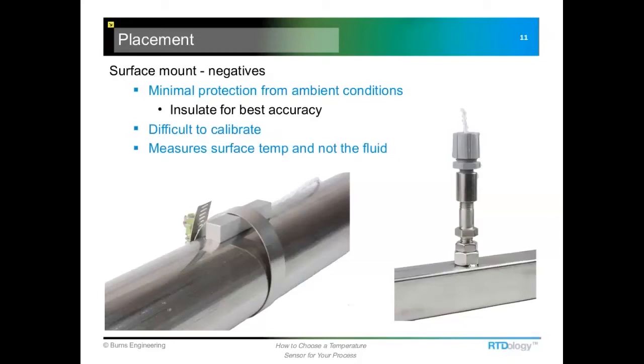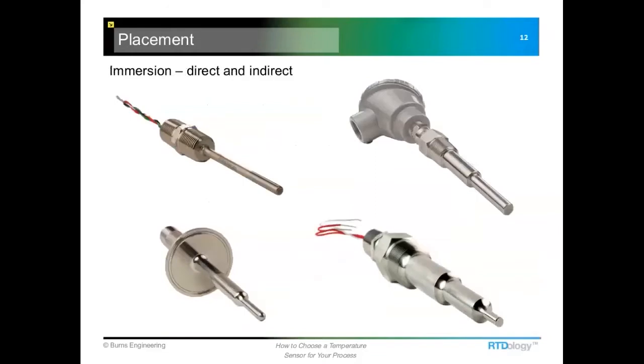There are some temperature transmitter probe combinations that have a little algorithm built in that estimate the fluid temperature in a pipe based on the surface temperature of the pipe. They seem to work fairly well. They're going to be quite a bit more expensive, and I think the number of fluids that the algorithm works with may be minimal, but that's another option to look at. The other option is to immerse the sensor in the fluid, and these typically give you a much better, more accurate measurement. We've got a couple of different styles. This is a threaded-in one, this is a sanitary fitting, and then a typical immersion style that uses a thermowell with a spring-loaded probe inside.